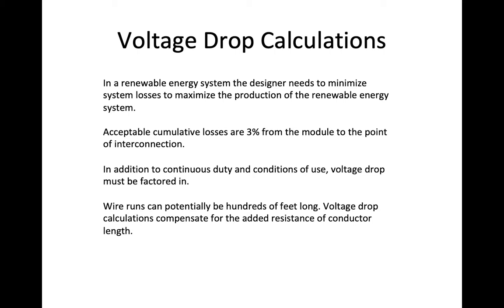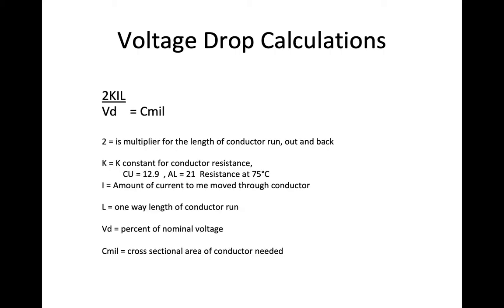So, this is the process. The formula is 2KIL over Vd equals Cmil. I'm going to put into this formula the parameters for my system. What am I trying to do? What is the voltage I'm trying to get from point A to point B? What is the current? What is the distance? And the end result will be the cross-sectional area, or the diameter, measured in Cmils.